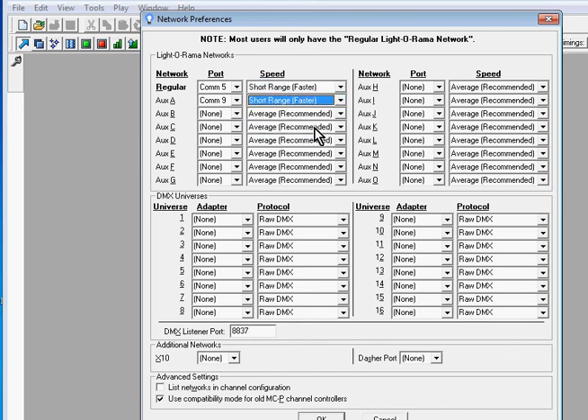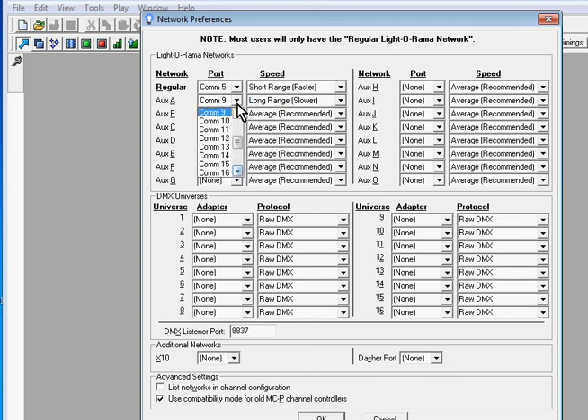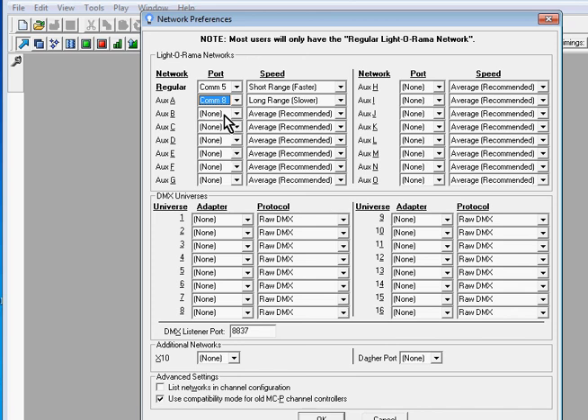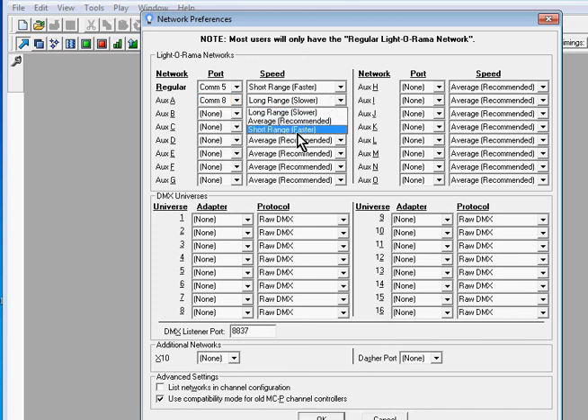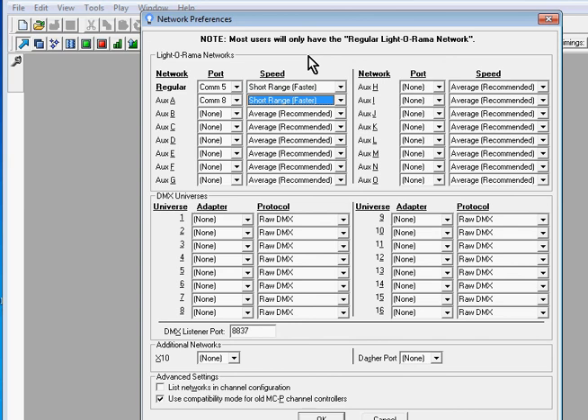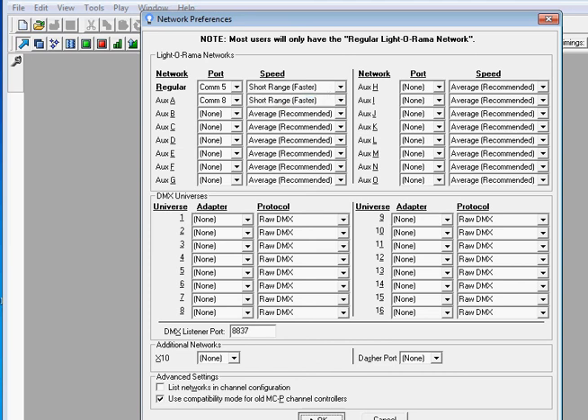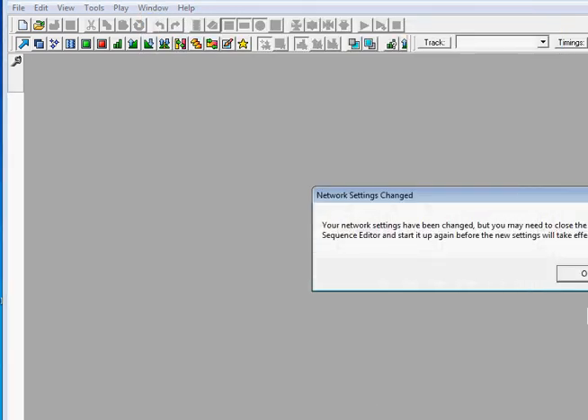So there now we've set the COM ports. Somehow that changed, OK that's COM 8, and that's short range faster. That's because I'm using my laptop here and this mouse is sort of flaky sometimes. So we have that set up properly. It's important to set short range faster because the CCR controllers will lag if you don't do that, they'll lag and not keep up with the sequence in some places. So we click on OK.